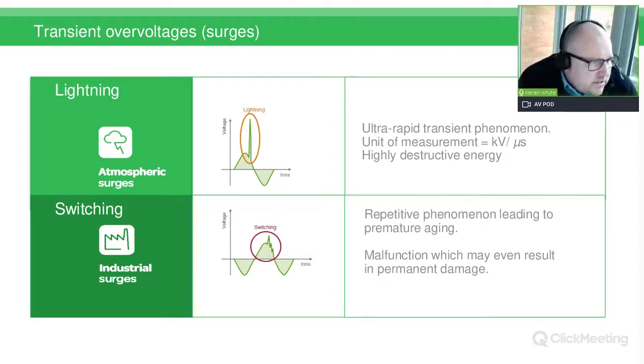Transient overvoltages, surges. From lightning, atmospheric surges, there we see the spike with a ring around it for a very short duration of time, but a very high spike. An ultra rapid transient phenomenon, unit of measure kilovolts per microsecond, and a highly destructive energy source. That normally is the type coming from lightning. If you look at industrial switching, if you live in an industrial area with factories and large units around you, you'll have a repetitive phenomenon leading to premature aging. So what we have here is a higher than normal voltage over a longer duration, which causes damage in a different way, premature aging, as opposed to the ultra fast lightning, which will be a one hit wonder.